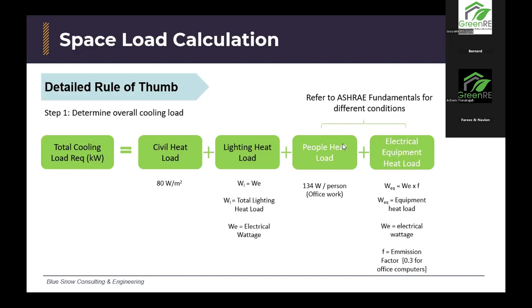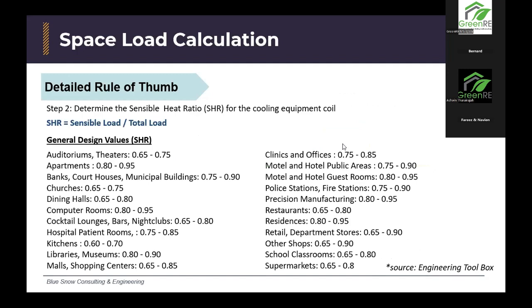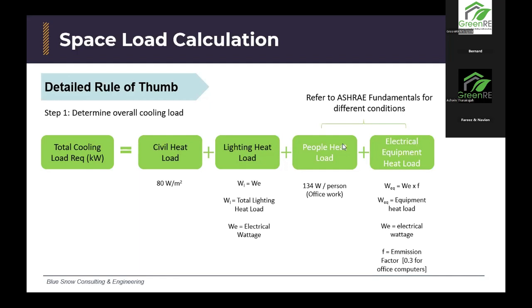A rice cooker may be 0.7, a microwave probably also 0.7, something like that. Let me show you an example, but before we go to the example, there's another thing we need to take into consideration when you're doing this rule of thumb. All this wattage you're calculating is what is known as the total cooling load or the total heat load. Total meaning it is a combination of sensible and latent. Like I said, if you mistakenly do not account for the latent, you may end up with humidity issues.